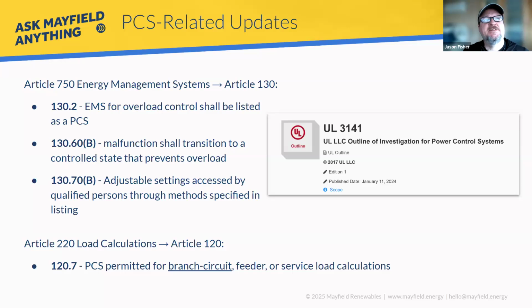This is why it's so critical to make sure that you fully understand the abilities of a PCS, or a product that claims it has PCS, and that it's fully documented, because it does have tremendous value. I'm pretty excited about this with regards to our electrical design stuff, where we will now be able to design conductors, bus bars, etc., not just for sources, but for loads as well, to the actual controlled load, and not some sort of predicted, likely-to-happen, worst-case scenario that's happened to us in the past. So yeah, for bus bar connections, I think that's going to be a big one.